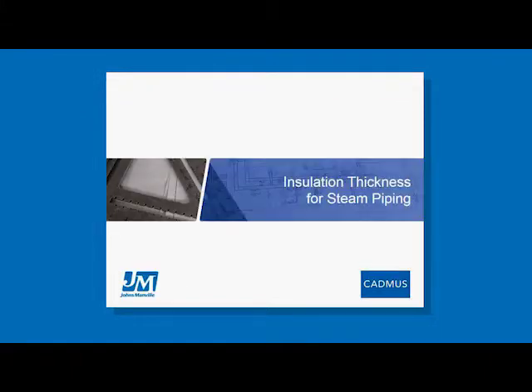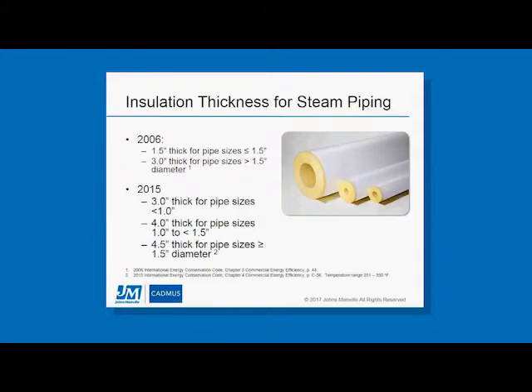The next example has to do with a code change involving the thickness for steam piping. In 2006, just 2 thicknesses were required. If the pipe size was less than or equal to 1.5 inches in diameter, the insulation thickness was 1.5 inches. If your pipe size was greater than 1.5 inches in diameter, then your insulation thickness needed to be 3 inches. Moving forward to 2015, with the energy savings requirements required by either ASHRAE 90.1 that Eric alluded to, or the International Energy Conservation Code, insulation thicknesses increased.